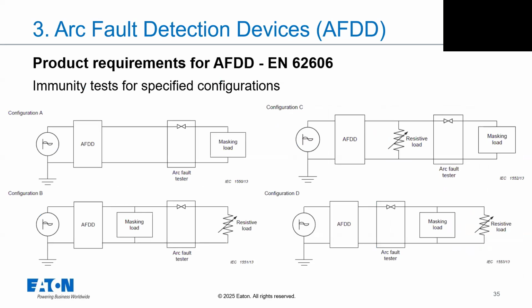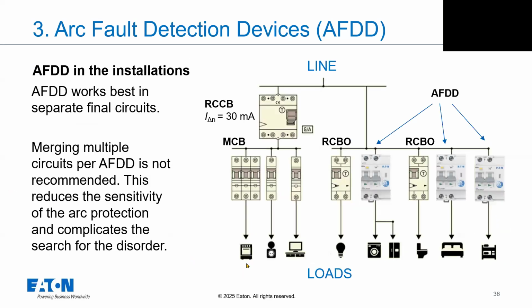And this is only for overview, I will not comment so much. What is in the standard for AFDD? It's good to mention one important thing. During testing, an arc is created, the AFDD is connected, and so on. But the standard describes conditions for a so-called masking load. It means you have two problems for the AFDD: detect correctly serial arc or parallel arc, and additionally ignore masking frequencies, for example, from a welding machine or something similar. And you can see that the standard describes various locations. Then you can be sure that in normal installations everything is working properly, because the AFDD is designed for various situations.